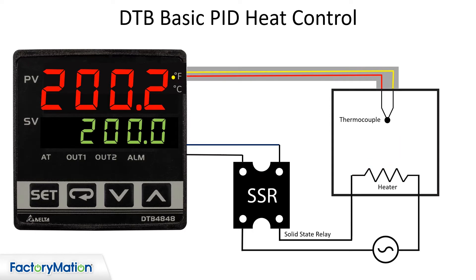The temperature in the system shown is maintained by the DTB using a thermocouple, a solid state relay, and a heater. The thermocouple provides a temperature reading to the DTB. Based on this reading, the DTB will trigger a pulsed output to a solid state relay which will energize the heating coil.